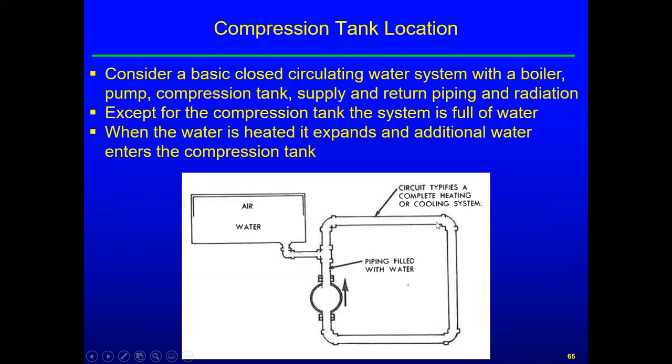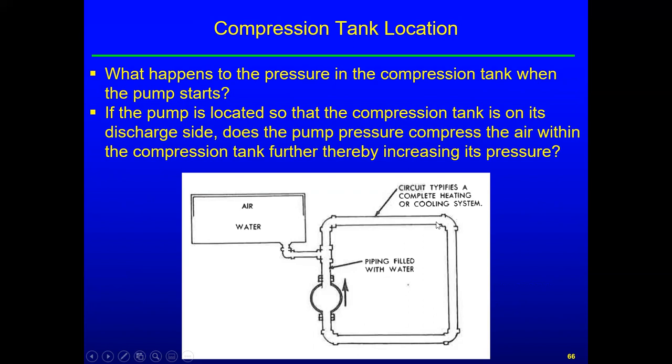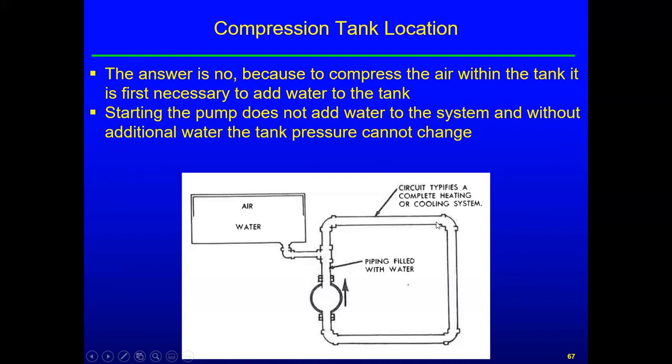Okay, what happens to the pressure in the compression tank when the pump starts? The pump is located so that the compression tank is on its discharge side, like we're showing here. Does the pump pressure compress the air within the compression tank further, thereby increasing its pressure? Well, when I first saw this, I thought, sure, turn the pump on, pressure's going to go up. Well, the answer is no, and we had a slide earlier that talked about this, because to compress air within the tank, it's first necessary to add water to the tank. Starting the pump does not add water to the system, and without additional water, the tank pressure cannot change.